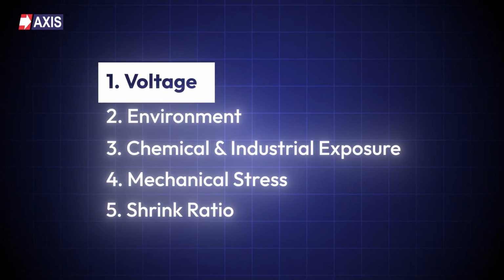Starting with the first and most important factor, voltage. Before you select any heat shrinkable product, you must ask one question. What is my system voltage? Is it low, medium, or high? In the case of power cables, low voltage usually means up to 1.1 kilovolts. Medium voltage typically ranges up to 36 kilovolts, and high voltage includes anything above 36 kilovolts. Your voltage level decides your insulation requirement.